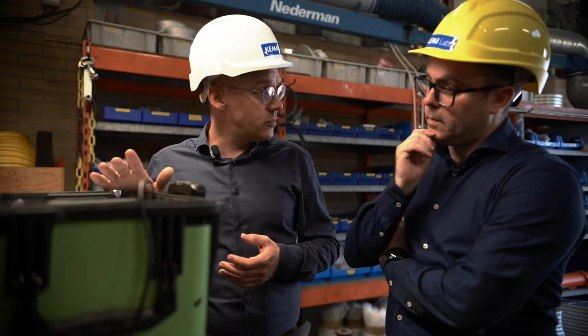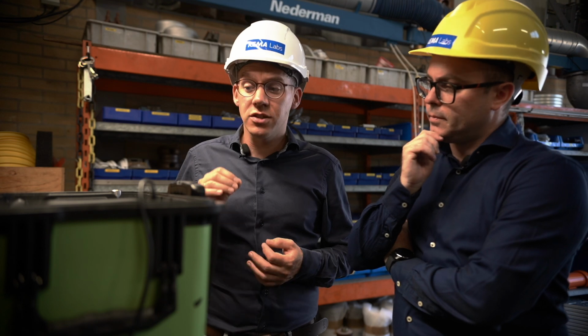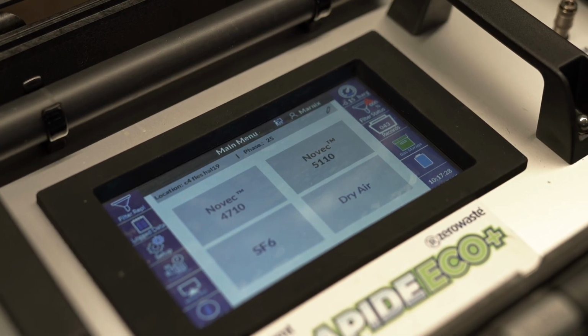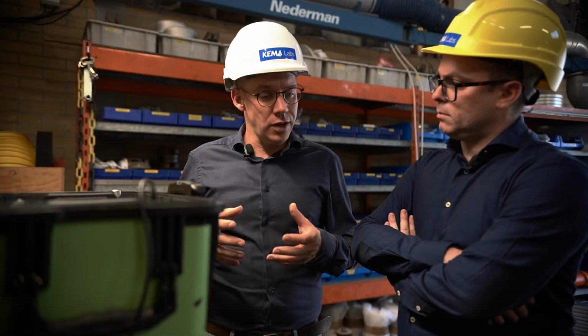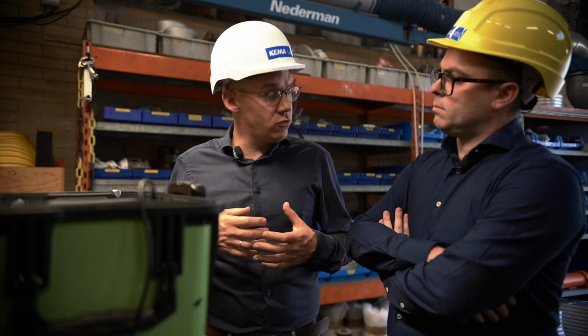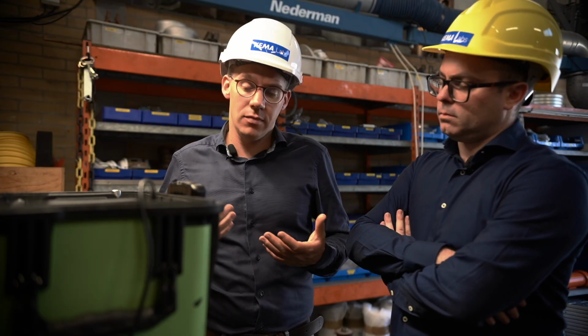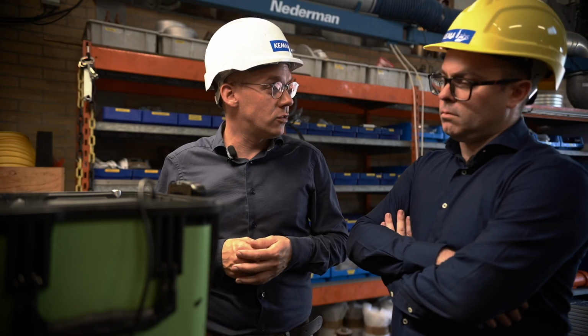Exactly, and for the customer this is critical, of course, to have this information. As KEMA Labs we had to push this a little, because with SF6 we would always mention that this is an SF6 type circuit breaker. But when alternative gases came, manufacturers claimed the exact gas mixture was their R&D secret, and didn't want to share it. As an independent laboratory, we find it important that it is clear what was tested in the type test report we provide to the customer. So in STL, but also in IEC, we worked to get this clarity identified in the report, so that anyone reading the report or certificate can clearly see how the product was tested and which gas was used, which is critical for the interruption capability of the circuit breaker.